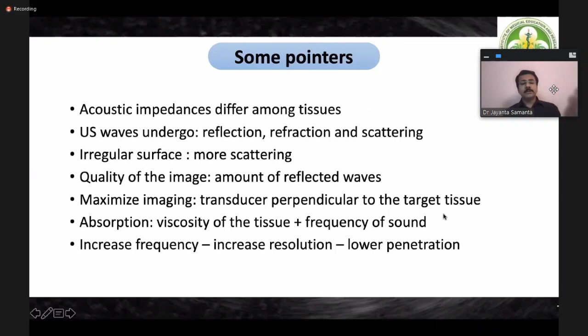Another important phenomenon that occurs is known as absorption. A good amount of the ultrasonic waves gets absorbed into the tissues. How much absorption occurs will depend on the viscosity of the tissue and the frequency of the sound as well. So absorption will lead to some loss of the ultrasonic waves. As a result, when we increase the frequency, we increase the resolution, but because of the absorption phenomenon, the penetration depth decreases. As we go on increasing the frequency, the resolution increases, but the penetration decreases. I'll come to this in detail slightly later on.